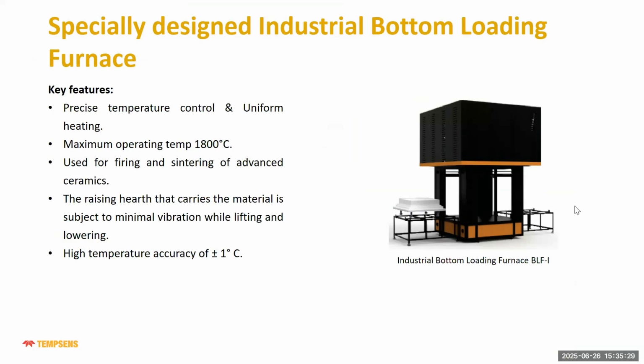If you want to heat your material and do a continuous cycle, we can do it. There will be two shuttles, one on each side, in which material will be loaded on one while the second is ready on the other side. When the lifting mechanism comes down, we can provide a second trolley inside the furnace, and it can be lifted up. So we can conserve energy by using the industrial bottom loading furnace.